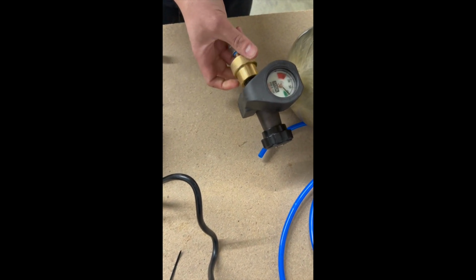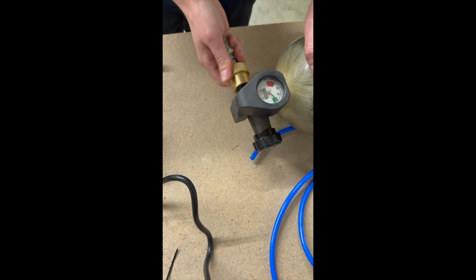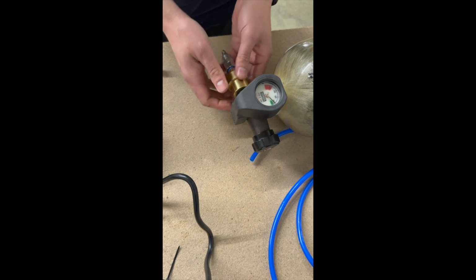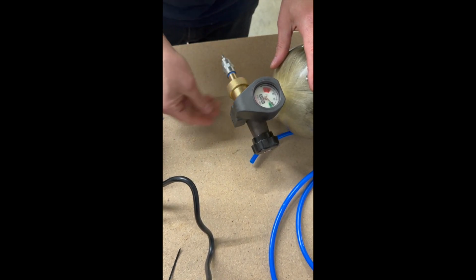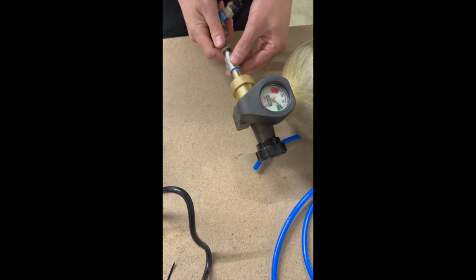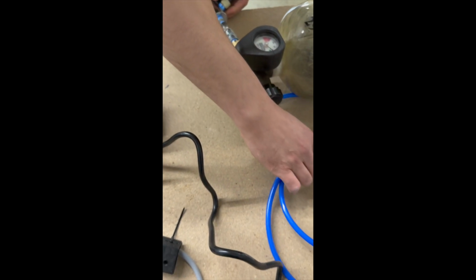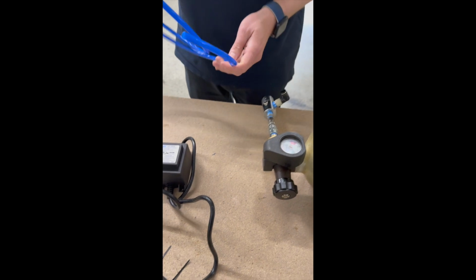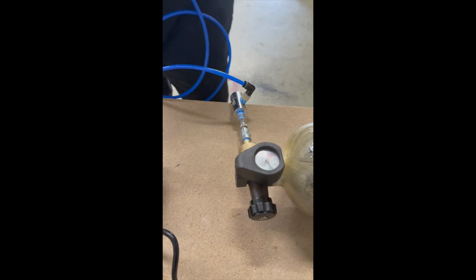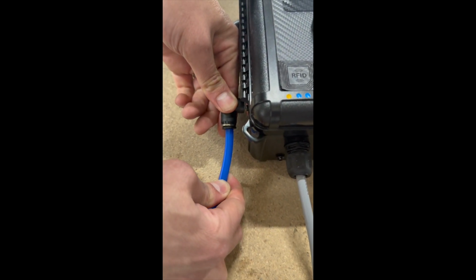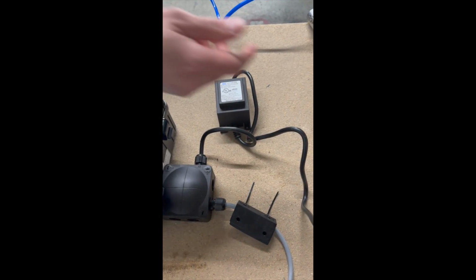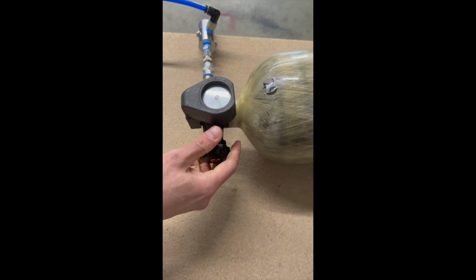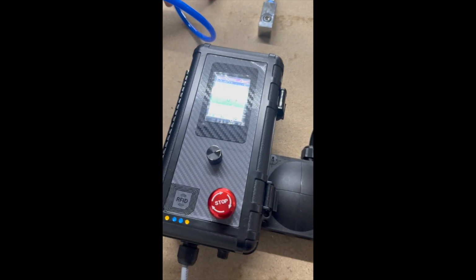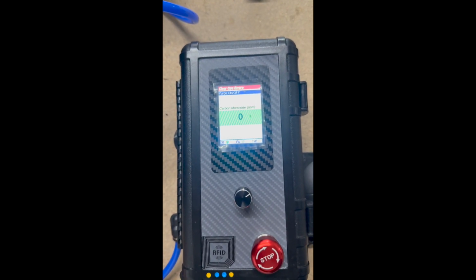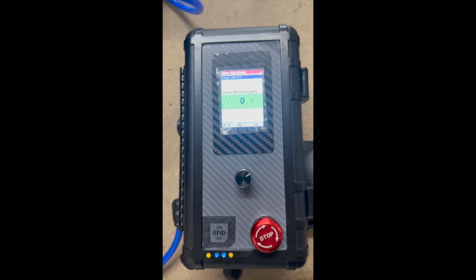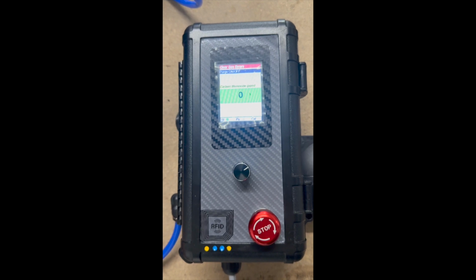On this one, I'll put my CGA valve on the tank. And I'll connect my regulator here with the quick connect valve. And I have a small pneumatic air hose that will be connected from the regulator to the CO monitoring. Now I can turn the air on and airflow will start to the monitoring tool. I hear airflow started. So right now this air going to the monitoring tool, it's checking the air against carbon monoxide.